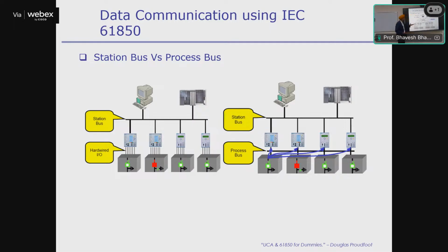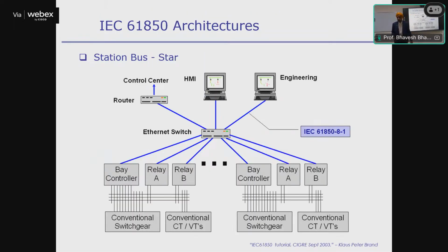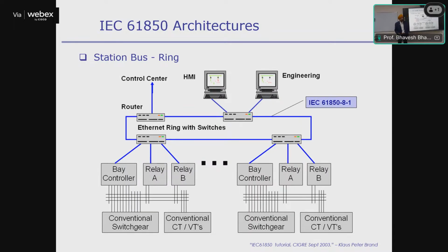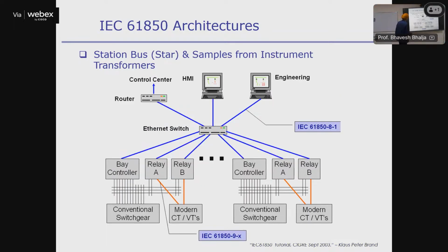So any possible architecture you can have. This is a star station bus, connected in star—these are hardwired conventional, but this is your station bus connected in star. You can connect in a ring bus, so any possible architecture that you can think of, or you can have a combination. Part of the station bus can be star, another part can be a ring.